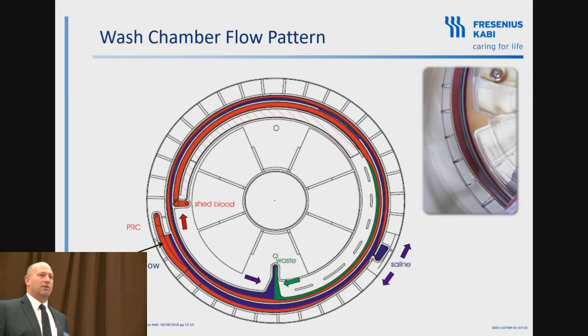This is kind of like putting it all together. This is looking down at the chamber. Blood comes in, goes around on the inside part of the spiral. You see the green, that's the plasma coming out. Keeps on going around, hits the saline port. Saline port pushes saline both directions, but retrograde is pushing back saline contaminants back into the waste port, so the waste port sees plasma from one side and saline and waste and plasma from the other side.